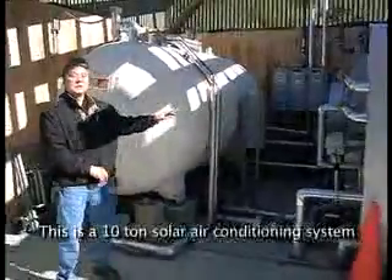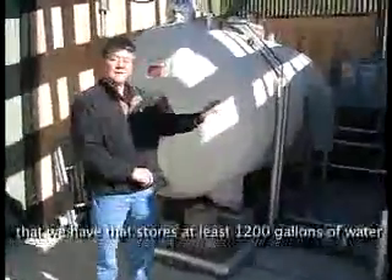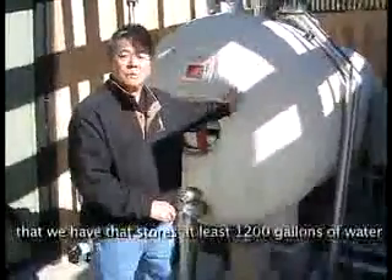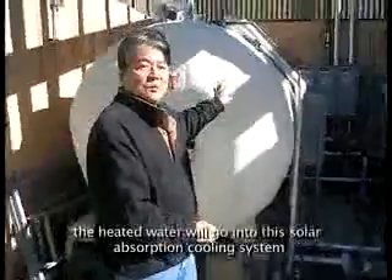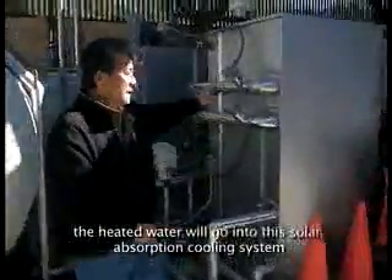This is a 10 ton solar air conditioning system that stores at least 1200 gallons of water in this tank. It's heated up to 200 degrees Fahrenheit. The heated water will go into this absorption cooling system that will separate the heat from the cold and create chilled water to chill the air conditioning.